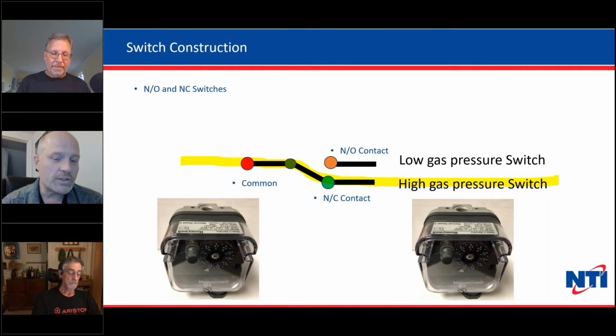So if the controller wants to lose power to something, then we would use a normally closed. And if we want, for example, to send power to something, then we would typically use a normally open contact. And so there's no rule for when you're going to see one or the other. It's application specific. Look at the wiring on the switch. It should tell you what it is.